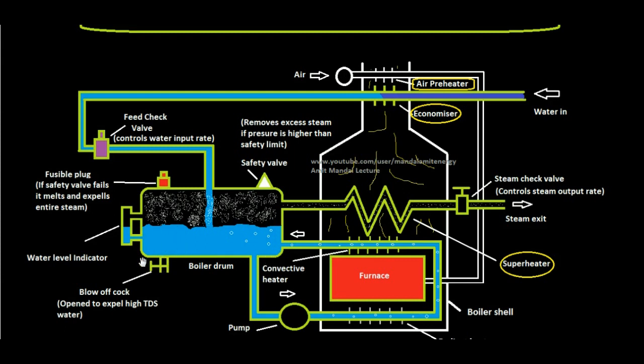It is required for reliable working of the boiler, because in case we do not apply it, the boiler will still work, but due to salt formation it can lead to clogging of these tubes and ultimately the boiler will fail to operate. The job of the blow off cock is to expel high TDS water, that is total dissolved solids. Actually these are the salts which are dissolved in the water. In case salt goes beyond a particular limit, those are expelled out. This is the job of the blow off cock.